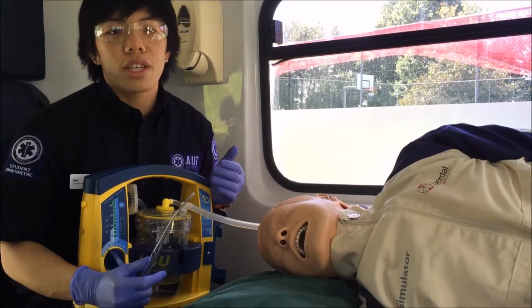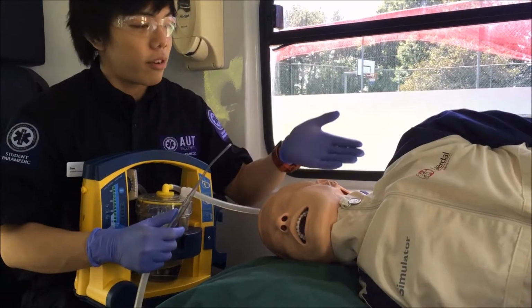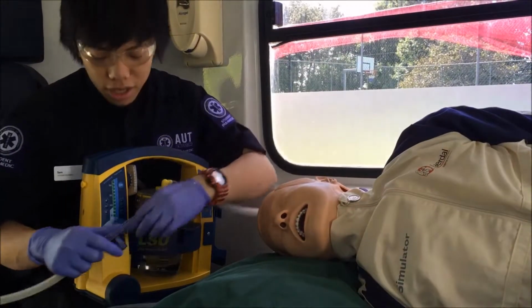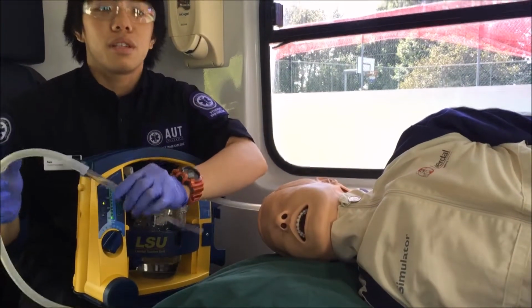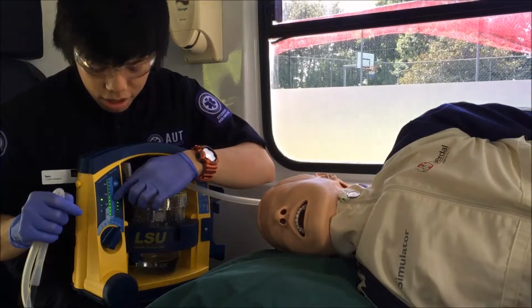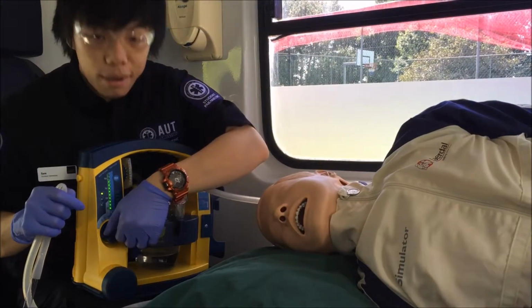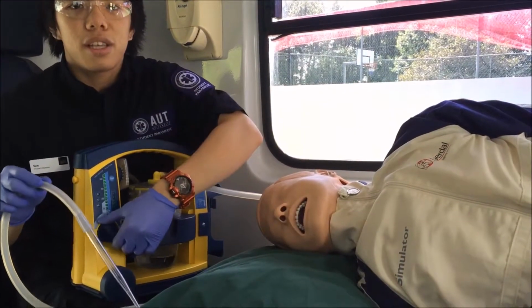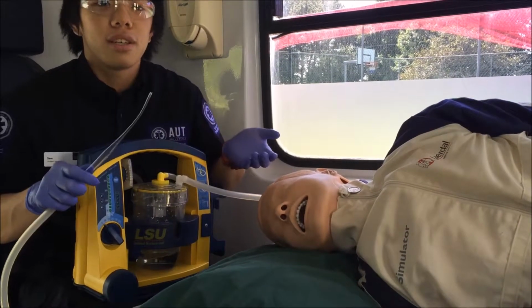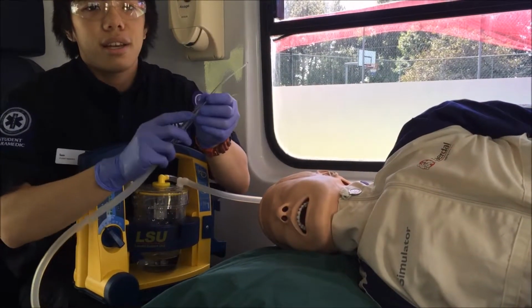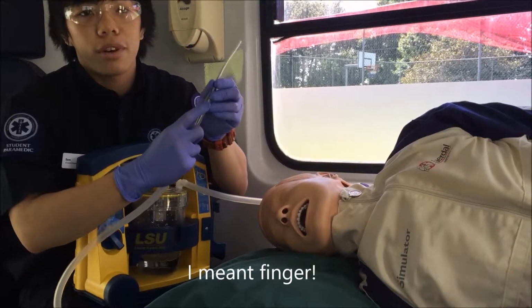Alright, so before suctioning, ensure that the patient is in a recovery position, and first test the suction unit by turning it on and occluding the tube until it reaches about 350 mmHg. If it does not reach that, troubleshoot for any leakages. There is a hole in the rigid catheter and it only suctions when I put my finger over it.